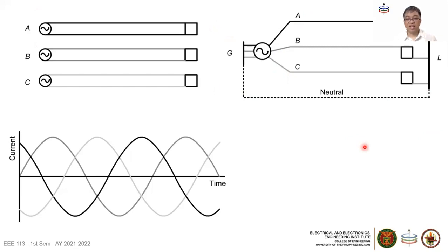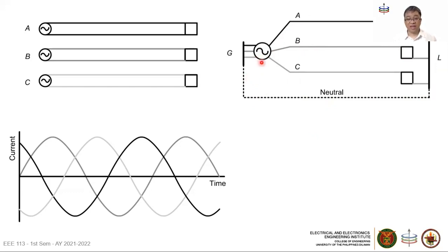The power and current through phase A can be delivered to the load and then return through the neutral wire back to the generator. For phase B, it flows through the second load and back through the same neutral conductor. So from six wires, we only need four wires — we have saved two wires for the setup.